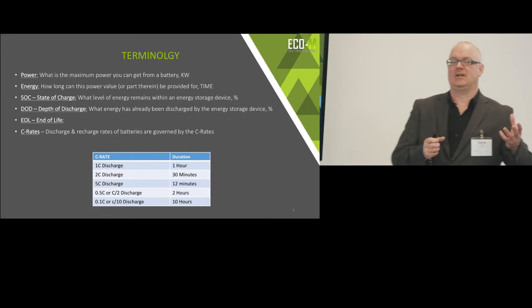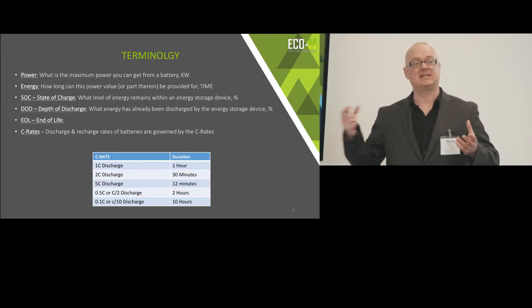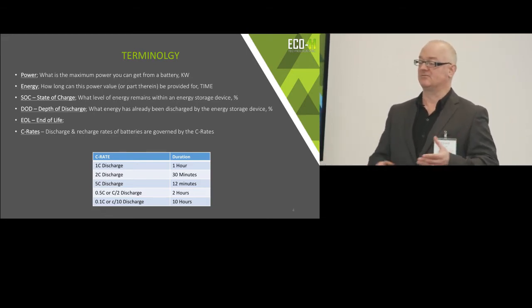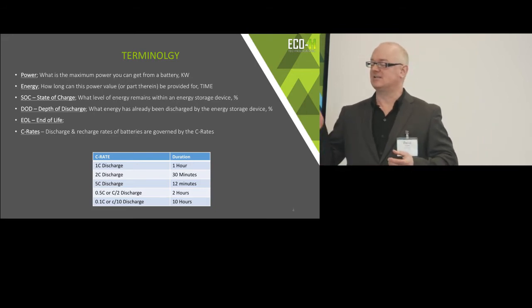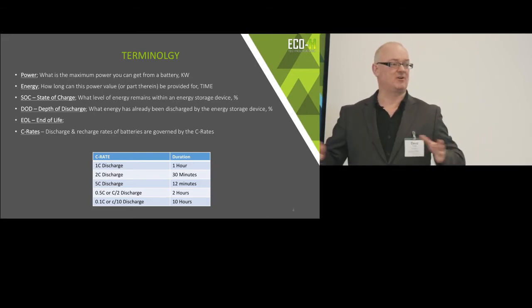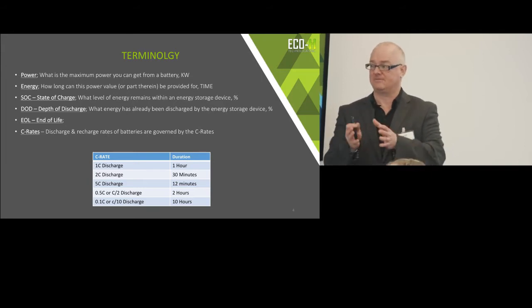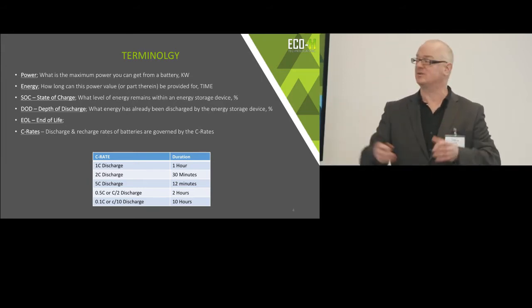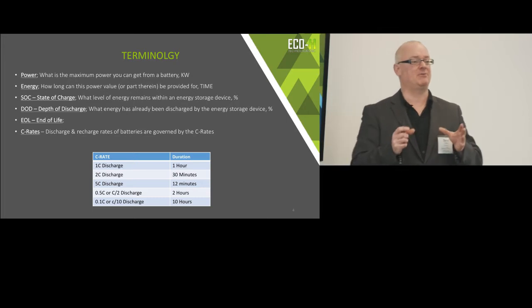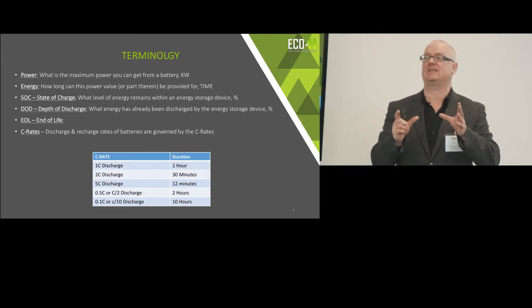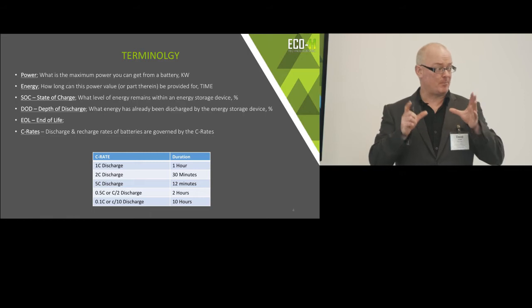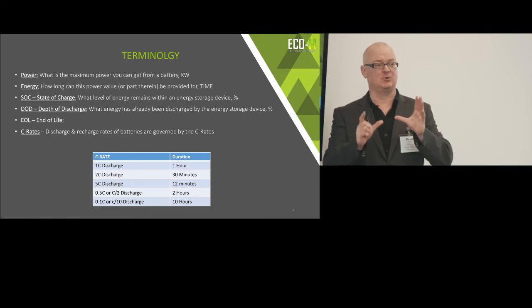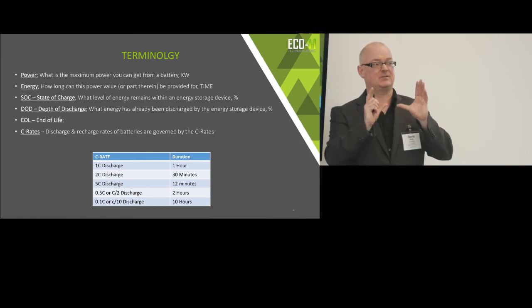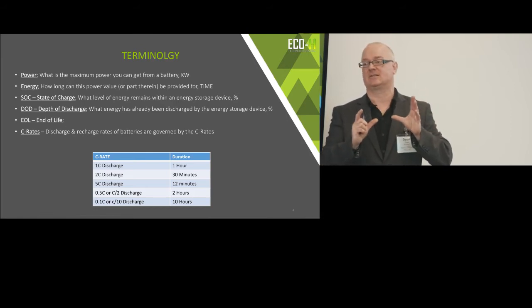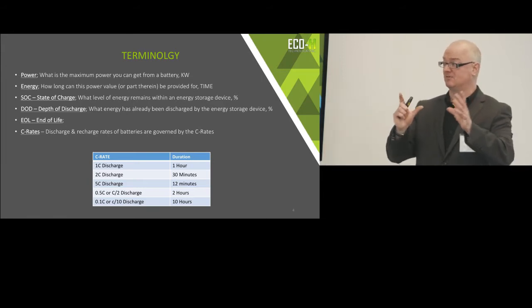BOL and EOL - BOL is beginning of life, EOL is end of life. The beginning of life is obviously a brand new system. EOL doesn't necessarily mean the system has to be thrown away or discarded at end of life. If it's got a 5-year warranty, 10-year warranty, or extended warranty, EOL basically means that you only have 70% of the available capacity to recharge. So if you have a 1 megawatt hour energy storage system, end of life means you can only now store it back up to 70% of its original capacity - that 1 megawatt hour system is now only 700 kilowatt hours.